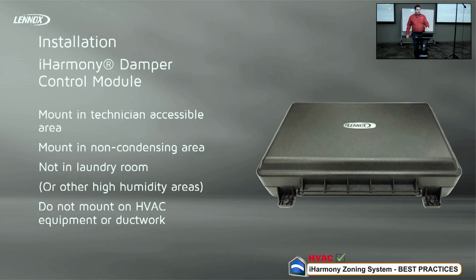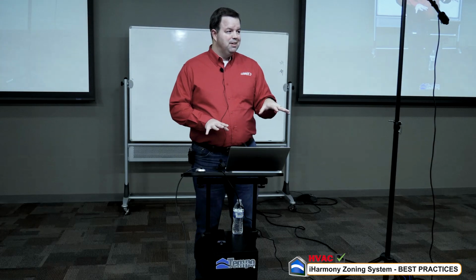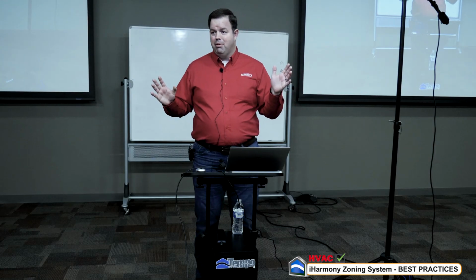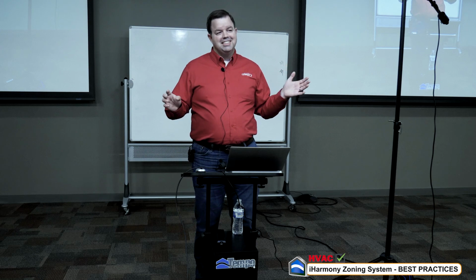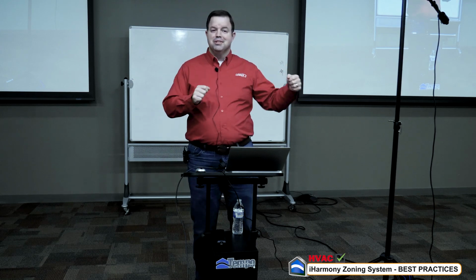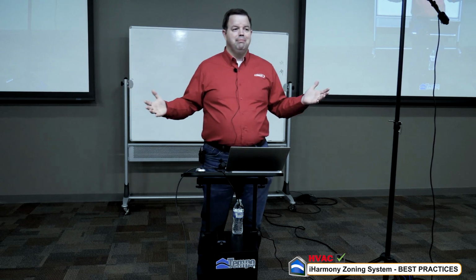One thing it mentions here is don't mount the panel to the AC equipment or the ductwork. That can be a critical component. Now, a lot of times when we give warnings like this, it's like, well, we've done a lot of them out there and haven't had any problems with it. And I always tell guys, it's not like once you run that zip screw into the plenum, the whole thing bursts into flames, right? That doesn't happen. But we end up with issues down the road, because sometimes it can be just the vibration of that panel that can cause some issues as we get air going through the plenum.